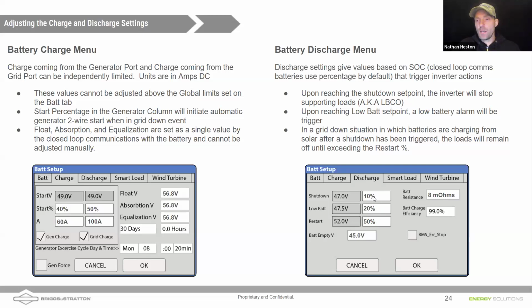When you hit the 10% setting here, it's going to shut the loads off. So you're going to lose power. And then if there's available solar and those batteries are climbing back up, once you hit the restart percentage, now if it was me, I'd probably set this closer to 30%, it will turn the loads back on. So the restart is the value. If those batteries are being charged from solar, that'll start supporting loads again. It'll automatically do that without you having to interrupt or intervene.